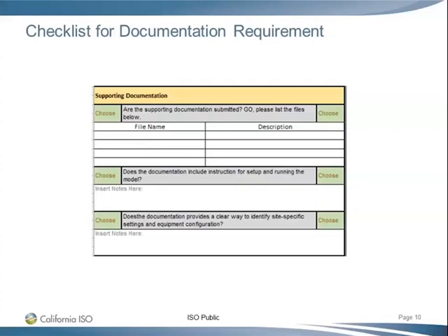I have one more, if you don't mind. I have one short question. At the beginning, you mentioned that when the GO is getting the black box model from the OEM, they need to customize it according to the site and submit it to California ISO. Does that mean that for the plant controller, as you know, a lot of these category 1 and 2 have a main plant controller that is communicating with the inverters for voltage control and power factor control, are we supposed to build that plant controller as a submittal too? Or can anything be handled through the inverter, like all the voltage control and the sliders for P and Q, as long as we get the same response? Do you need us to mimic that plant controller that is sitting at the POI in the PSCAD model?